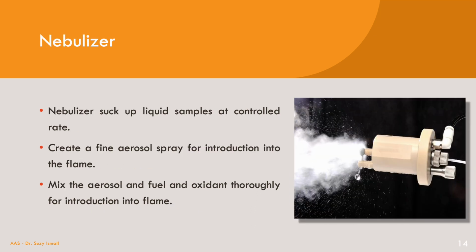The nebulizer sucks up the liquid sample at a controlled rate. That is the initial part, when you put your sample in a bottle or in a beaker. The nebulizer plays its role to suck up the liquid sample, and it creates a fine aerosol spray for introduction into the flame, and before that it mixes the aerosol with fuel and oxidant. Hopefully you are able to look back at our previous flow of how the AAS processes the sample, right?